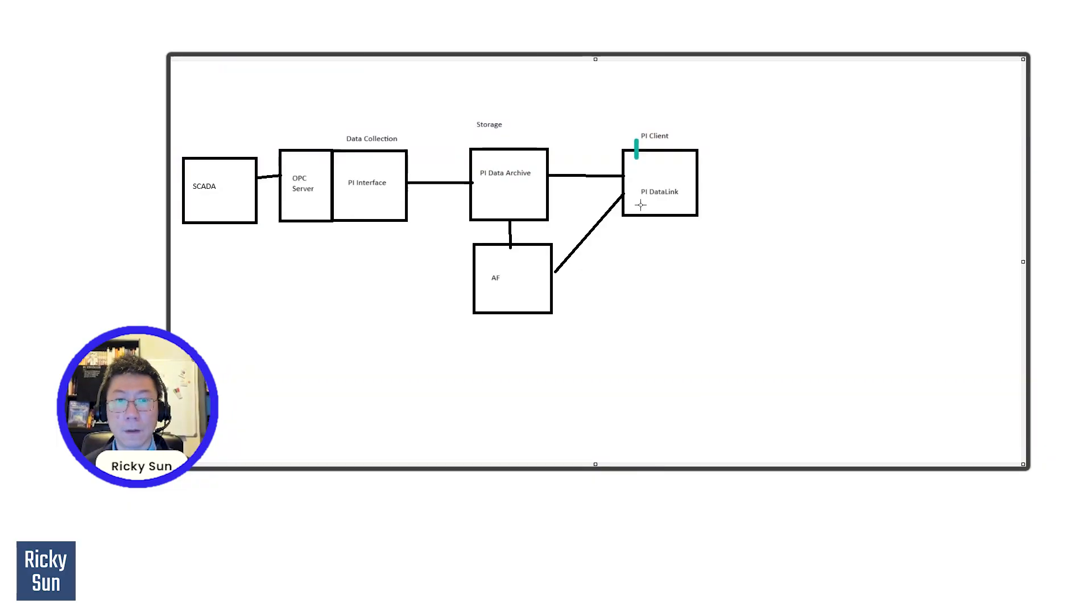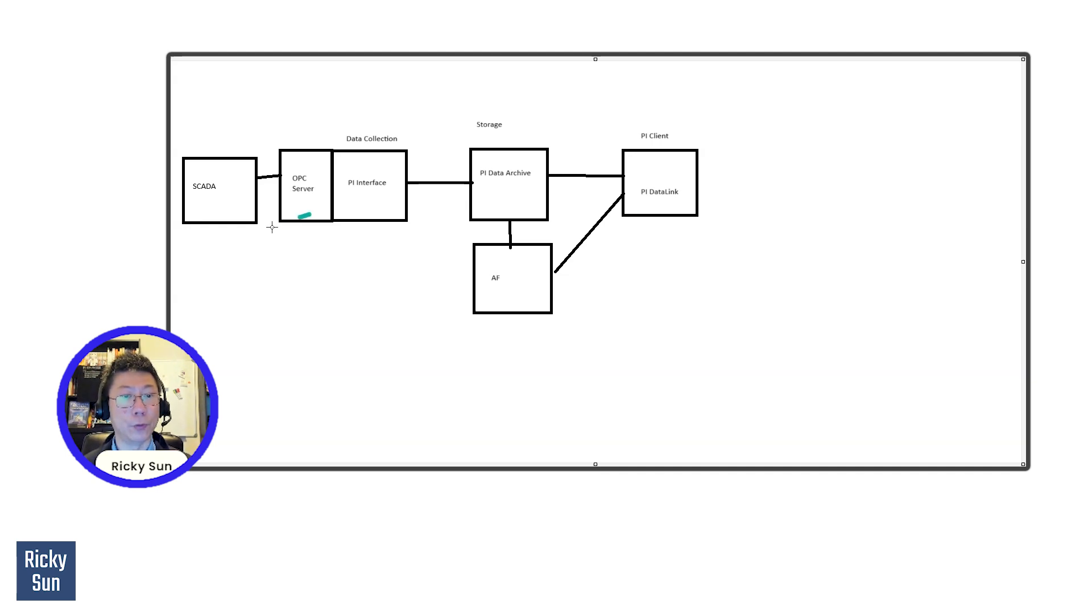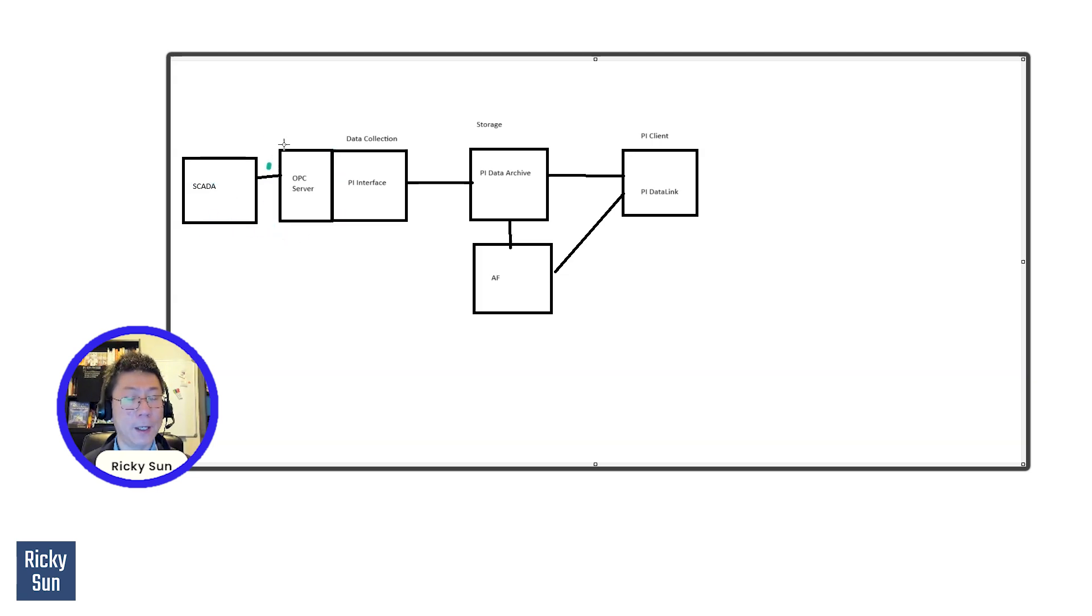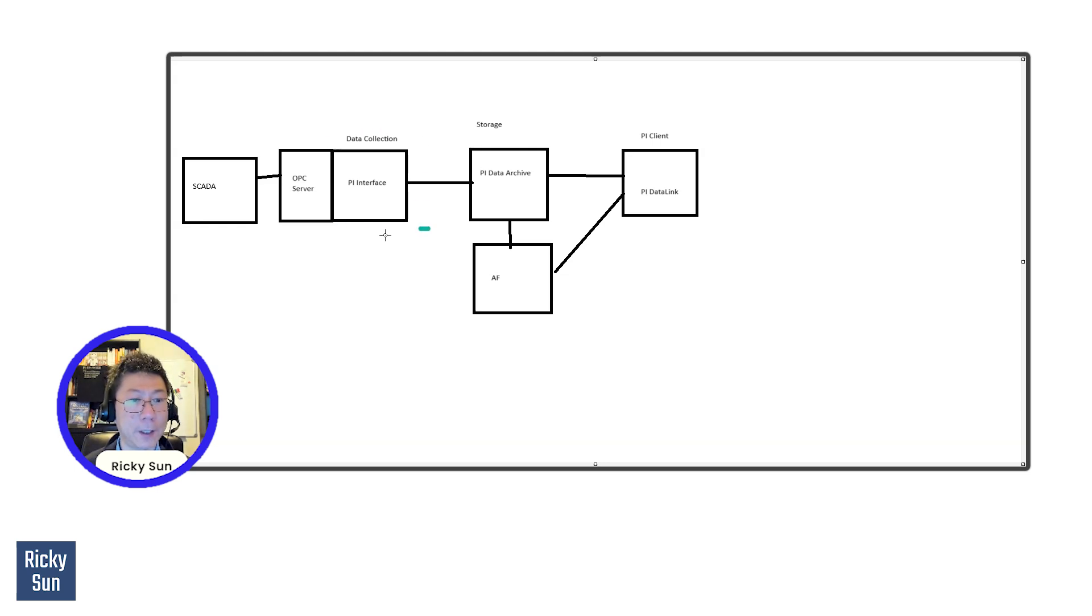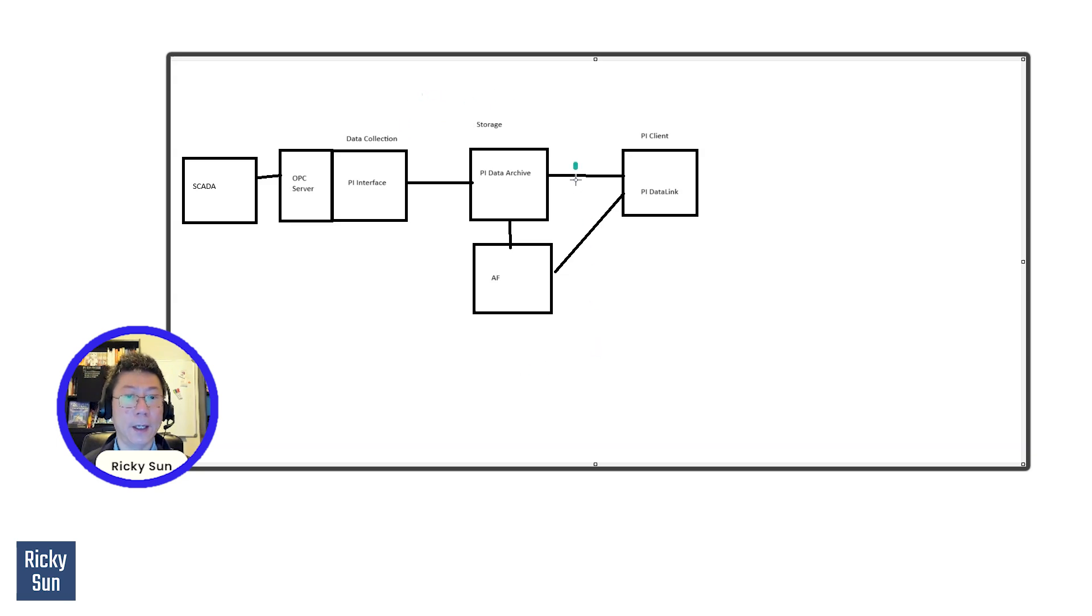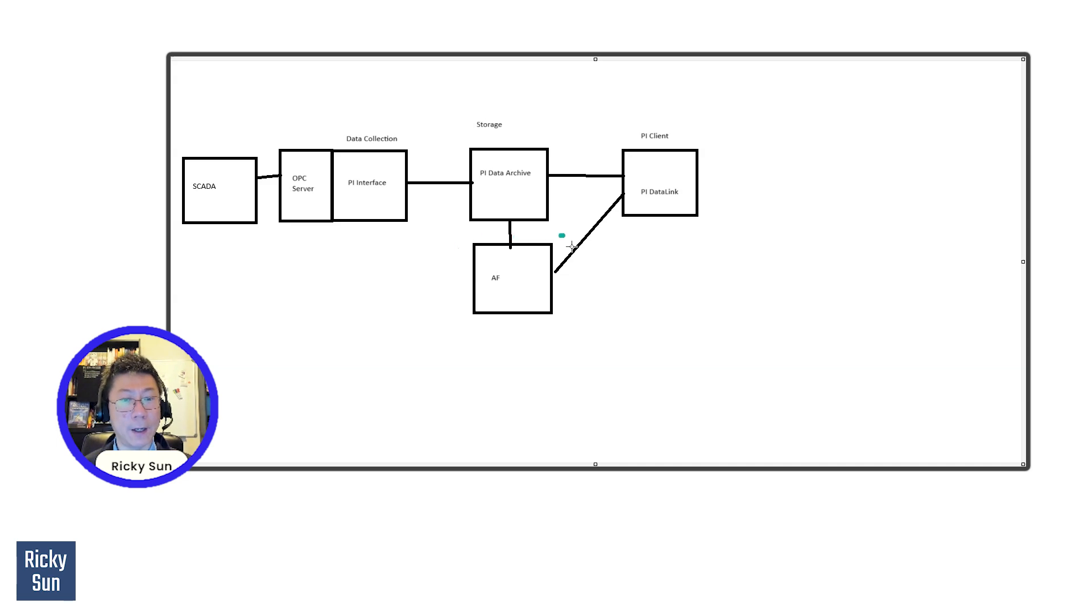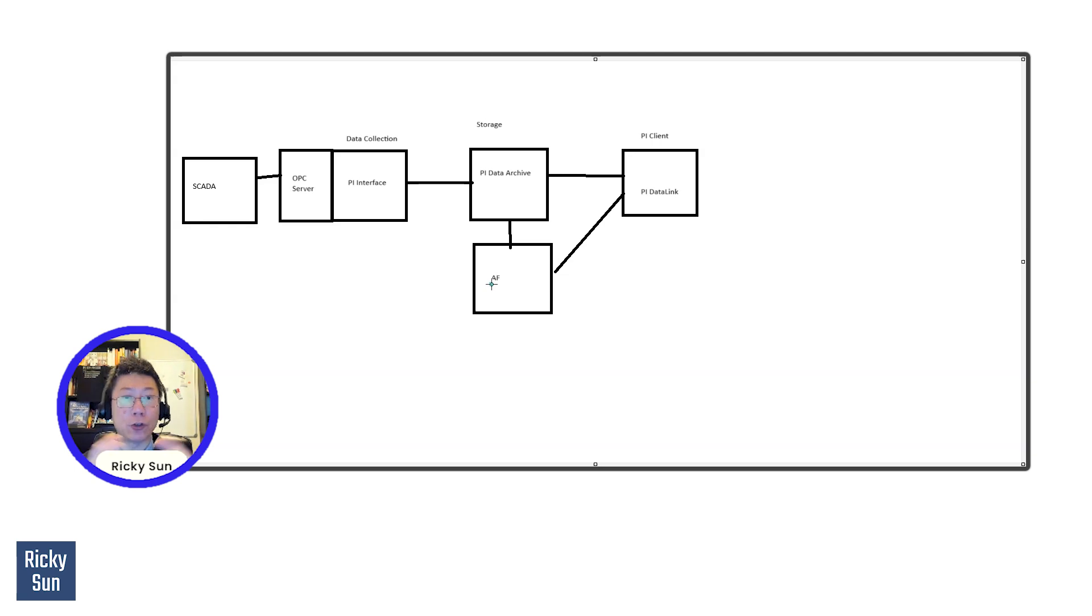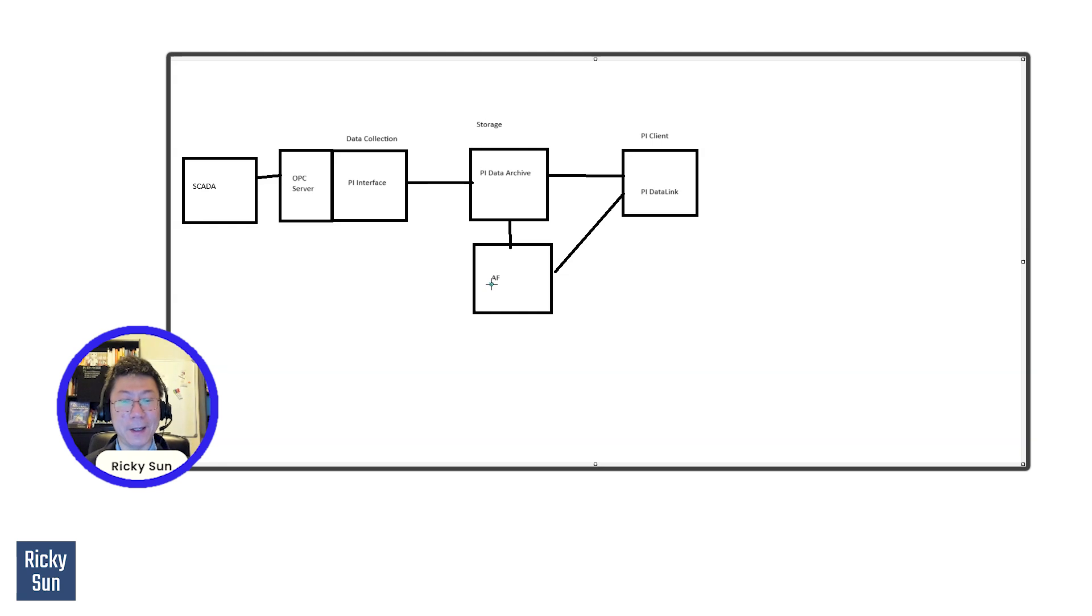And let's talk about the architecture. So this is the architecture of how data gets to Excel. You can have a SCADA system, and then the SCADA system has an add-on to become having OPC servers. And then you can buy a license from OSIsoft to collect the data through the PI interface. It could be connector, it could be adapter, and then send the data to PI server. That's where the storage is. And PI server has tags. And if you create an AF structure, you need Asset Framework. So this is Asset Framework where you can structure your data so you can find your data easier or other people find your data easier.